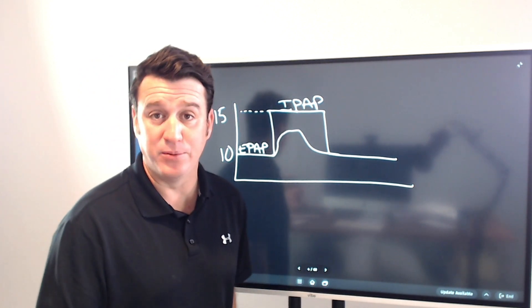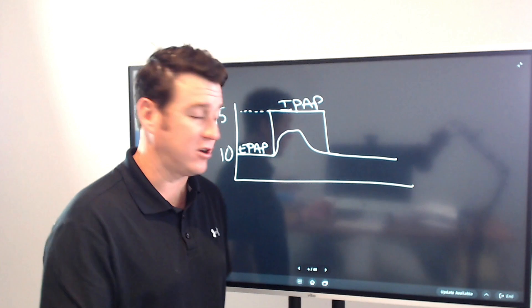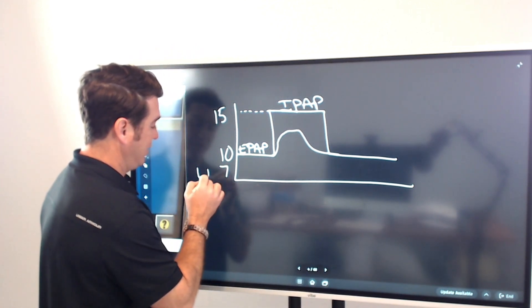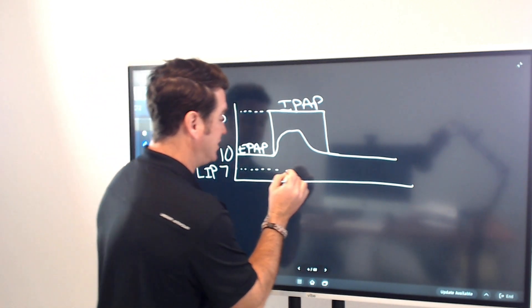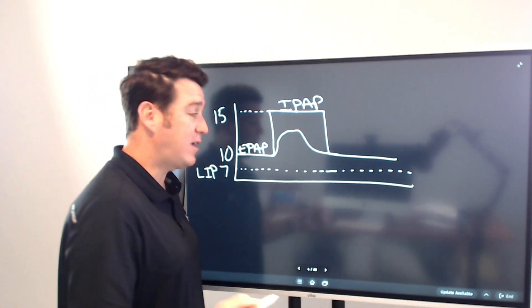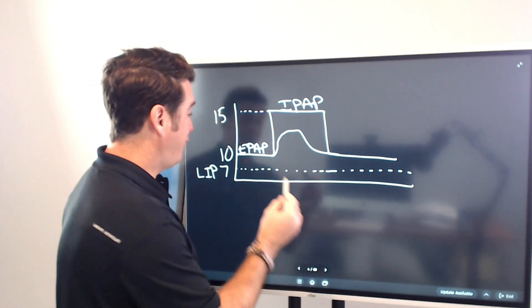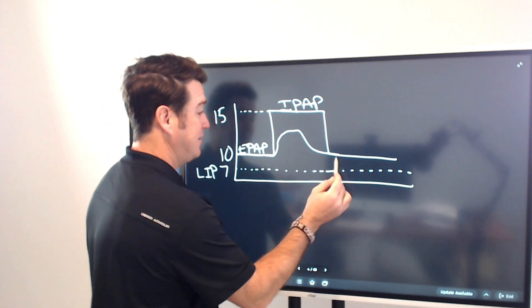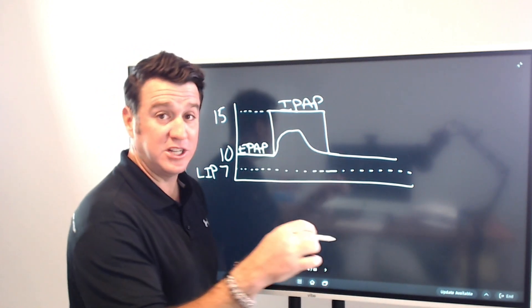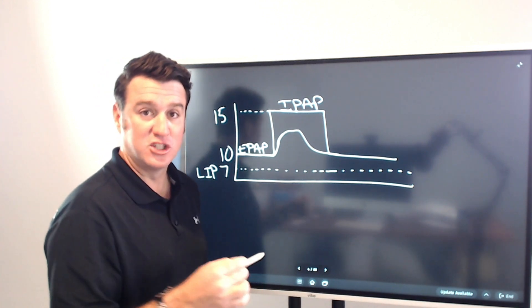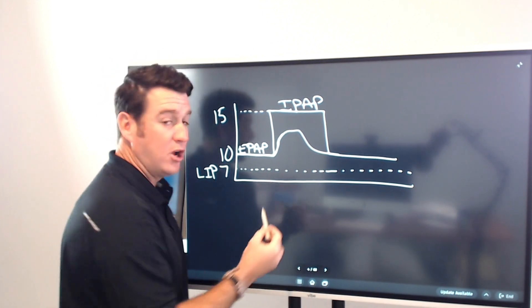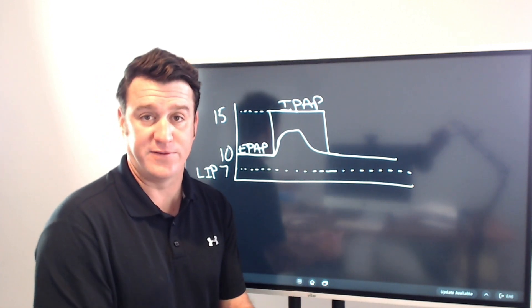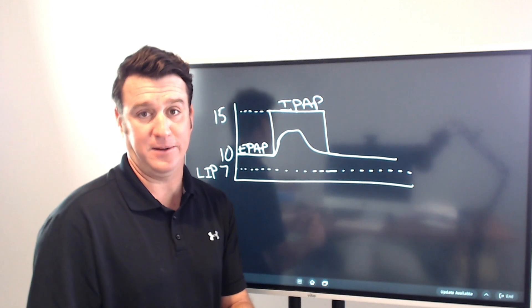Now, remember where the lip was set at? When I say lip, I'm talking low inspiratory pressure alarm. The lip was set at 7. This is where our lip was. That means the alarm was set here. Think about this. If we are holding EPAP at 10, then on inspiration, we are going to be going up from 10. So, in other words, this alarm right here will never go off because it is not set appropriately.